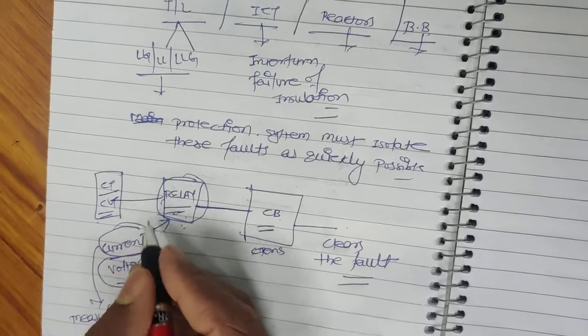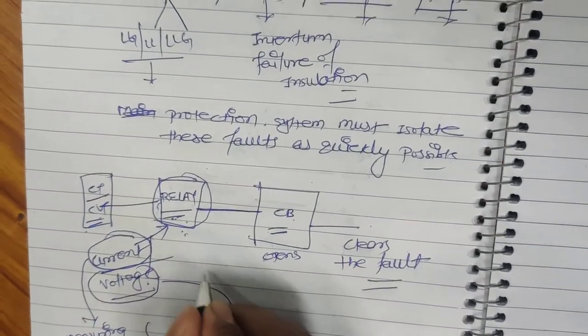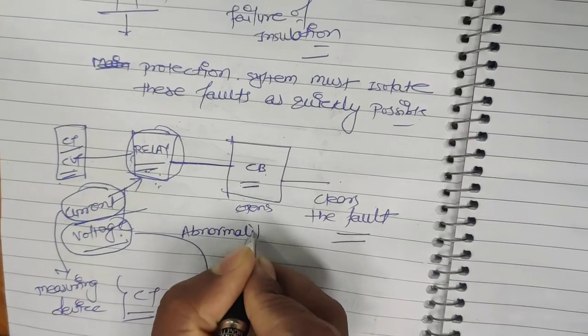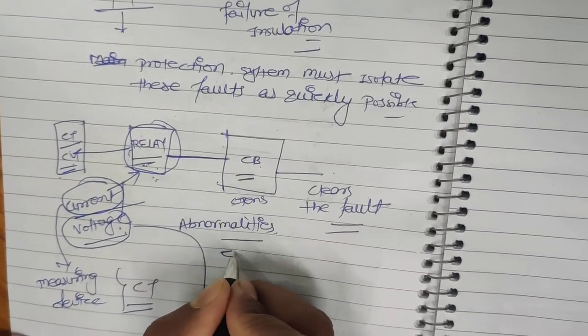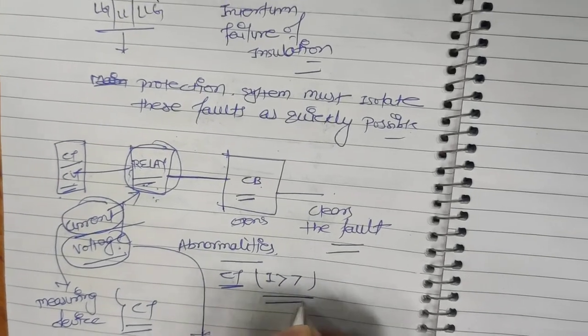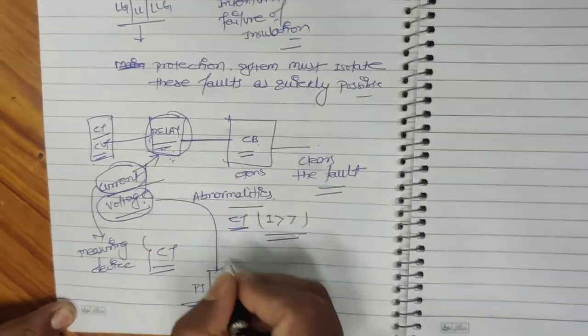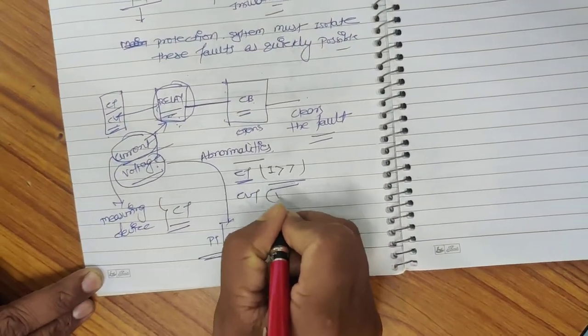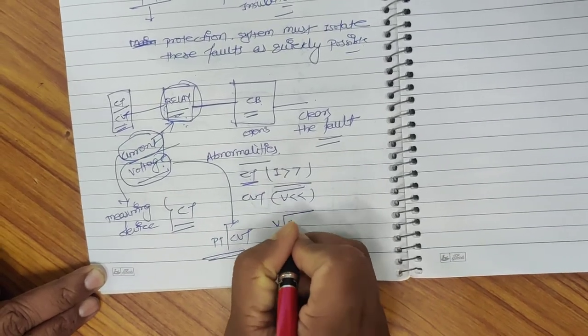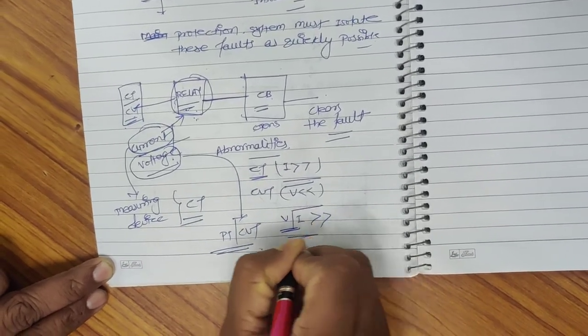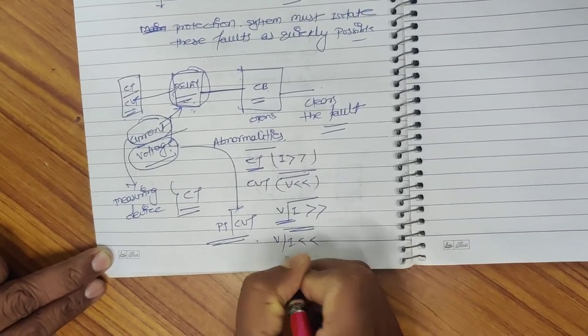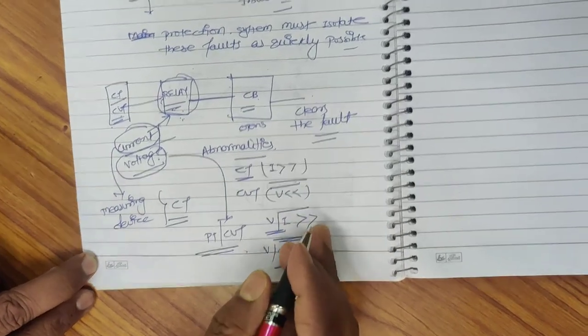The relay, after detecting the current and voltage signals, identifies any abnormality using its algorithm. For example, if the current from the CT is more than the set value, the relay detects it as an overcurrent and operates. Similarly, from the CVT, if the voltage drops below a certain value, that is under-voltage, and the relay will operate. Or, if the ratio V/I is more than or less than some set value, the relay will operate — depending on what kind of algorithm is being used.